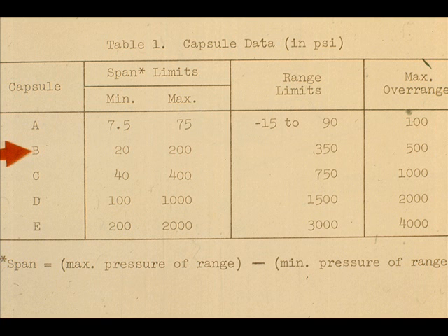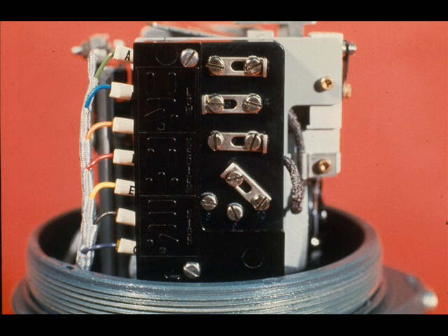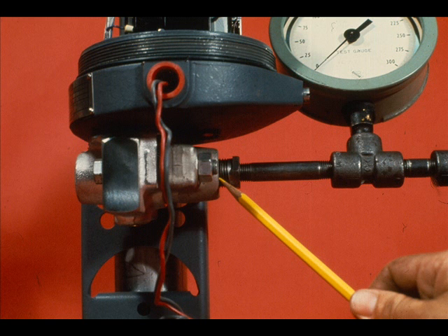Can we calibrate capsule B to 0 to 200 PSIG? The answer is yes. The maximum span is 200 PSIG and the range limits are minus 15 to 350 PSIG. For capsule B, the spans from 100 up to 200 PSIG require the high link arrangement.